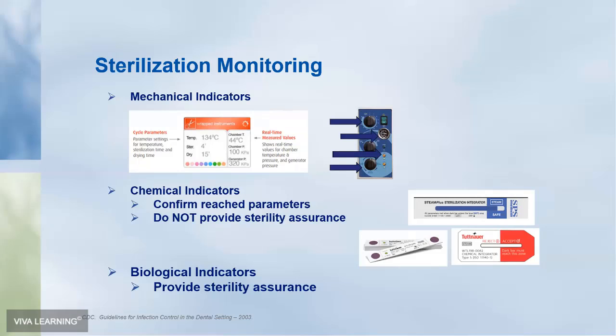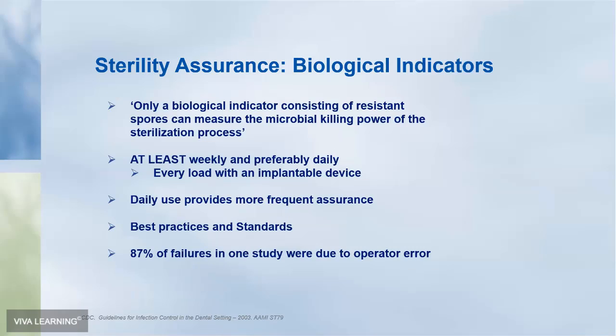The biological indicators provide sterility assurance. Only a biological indicator with resistant spores can measure the microbial killing power. And that's because the spores are at the top of the totem pole, if you like, for resistance of these microorganisms. So if the spores have been killed, the less resistant microorganisms have also been killed. The CDC recommendation is to perform that at least weekly, and it should preferably be performed daily. The other aspect is every time an implantable device has been sterilized, a biological indicator has to be included.